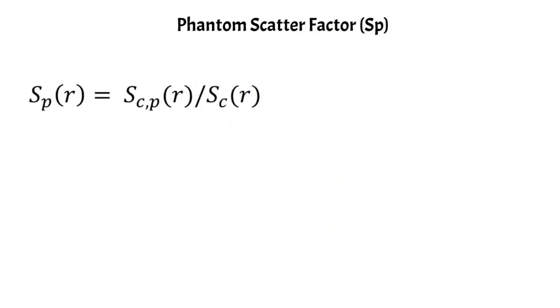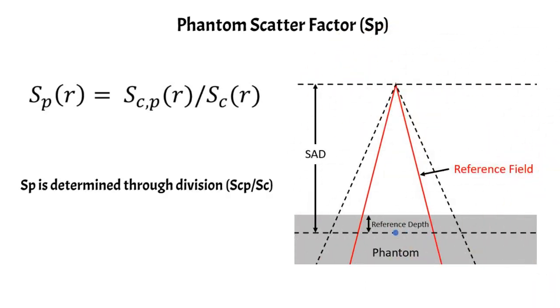Now we can talk about the phantom scatter factor, Sp. The reason it's introduced last is because there is no way to directly measure it — there's no way to differentiate a photon that originates in the phantom from one that originates in the treatment head. Because of that, we actually measure the total scatter factor and then determine the phantom scatter factor by dividing out the contribution from the treatment head. It's a factor we use in hand calculations, but we can't measure it directly; we have to determine it this way.